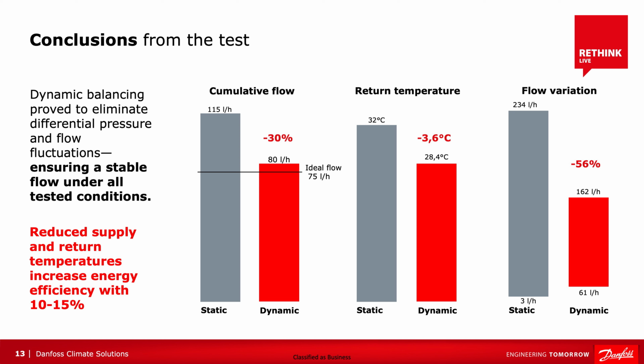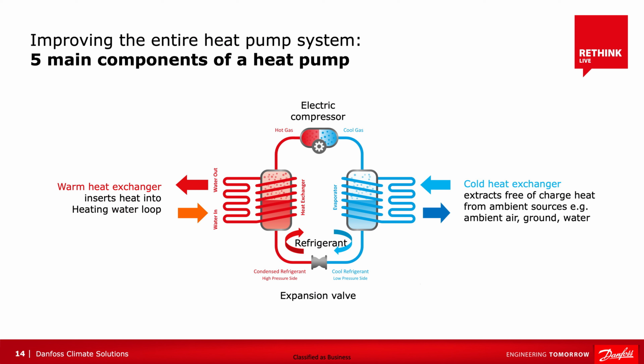In addition to talking about balancing, we have to look at the heat pump itself. Like any vapor compression system, we have a set number of components: a compressor, a hot side heat exchanger, a cold side heat exchanger, and a metering device or expansion valve. In a reversible heat pump, the refrigerant can move one way or both ways. And when we have flow stability on the heat pump system, the fluctuations when we're on and off are more stable.